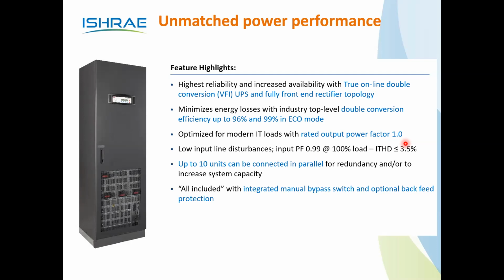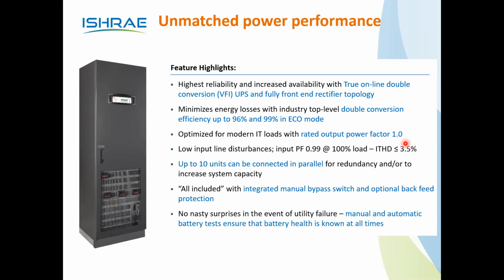Now manual bypass and static bypass, everything is built into the UPS system. Nothing is additional, no need to worry about it. Everything has been put in one box. And apart from that, we need to ask how the battery testing is going to be, whether manual or automatic. Both options should be available. It is already there in the technology. The customer needs to ask, I need automatic battery test.